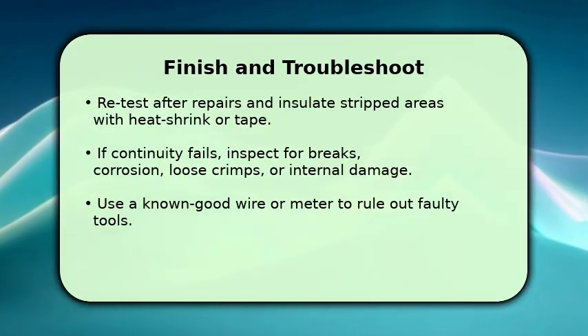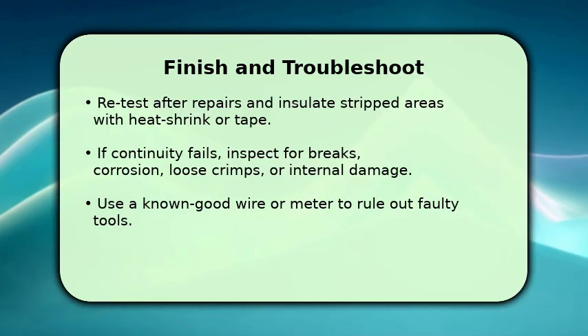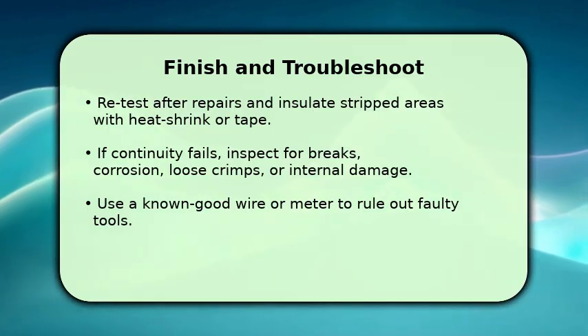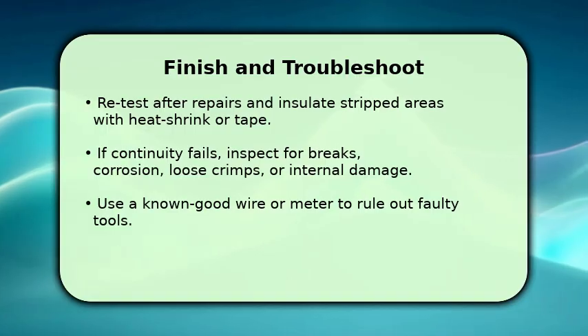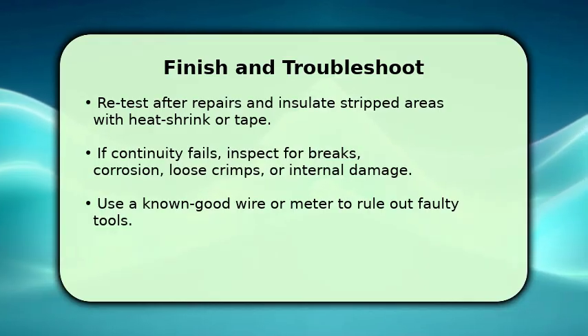Also verify your multimeter and probes are working by testing a known good wire or touching probes together. One key troubleshooting tip: swap in a known good meter or wire to isolate whether the problem is the tool or the wiring.